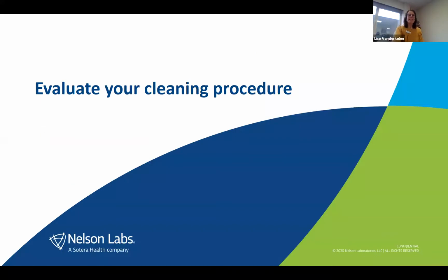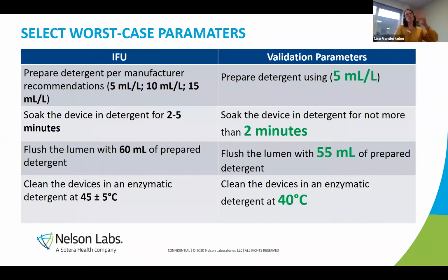Okay. What is the cleaning procedure that you're going to validate? So you have to select the worst case parameter. So on your left side, you have your IFU, your instructions for use, with the parameters described there. In your validations, you're going to challenge that method by taking the worst case, which means, for instance, in the first row, the detergent concentration can be from 5 up to 15 milliliters per liter. In a cleaning validation, you will use the lowest concentration, 5 milliliters per liter in this case, because that is worst case from a cleaning perspective. You will also use a shorter contact time, shorter duration. You will flush with a little bit less than is described, and you will use the lowest temperature.